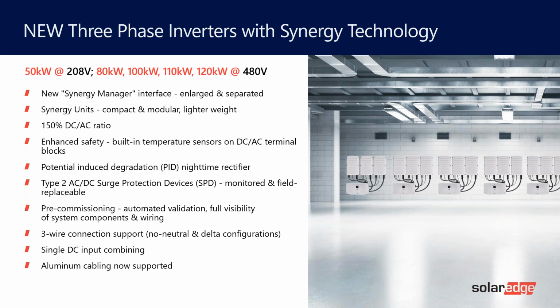The other thing is, out of the box now, all of our commercial inverters will operate up to 150% DC-AC ratio. So the process that we used to go through, where people would ask, hey, can we go above 1.3, the waiver process, you no longer need to do that. Out of the box, 150%.